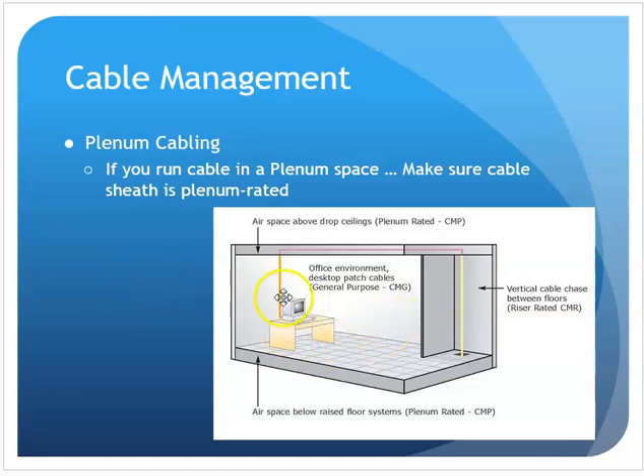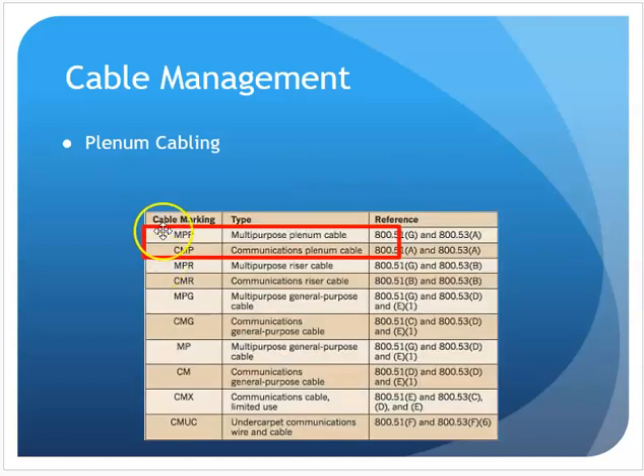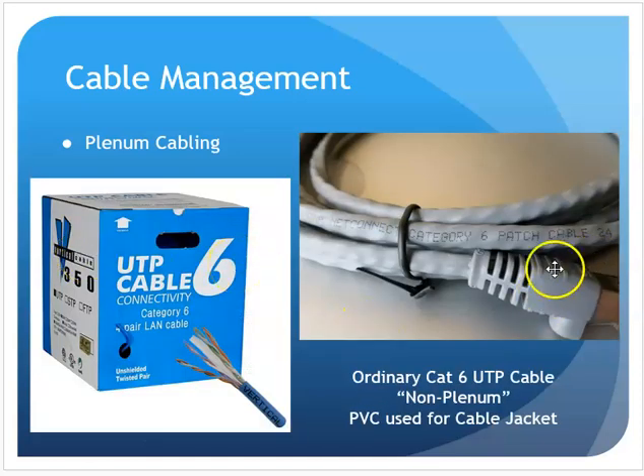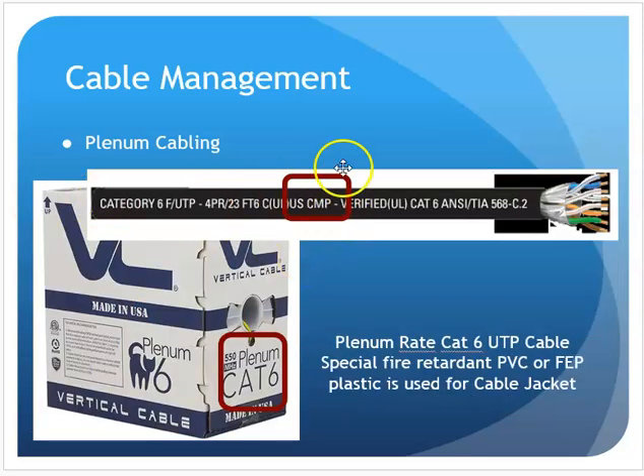So there are ratings: if I have a patch cable in a room, it could be general rated. If I'm going between floors, it can be riser rated. And if I'm installing above a ceiling or even potentially below a floor, that's a plenum space, and it would need to be plenum rated. And when I get cabling, there's a code that I can look for to show whether it's plenum or not. If I look at this box here, and I look at the cable here, this is showing this is just plain old patch cable. So that is not plenum rated cabling. Meanwhile, if I look over here, category 6, this shows me just kind of basic cabling, if you will. Here, as I look at it, I see CMP, that is plenum rated cabling, and the box tells me it's plenum rated cabling. So I would need to look for that if I'm installing or purchasing cable to install.